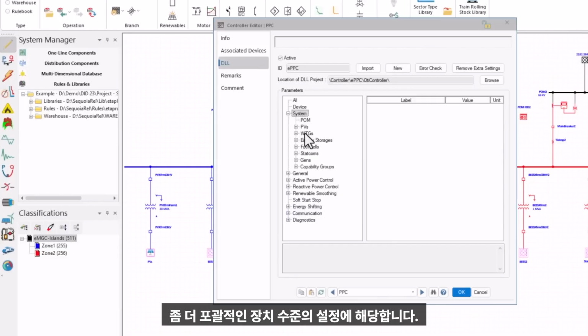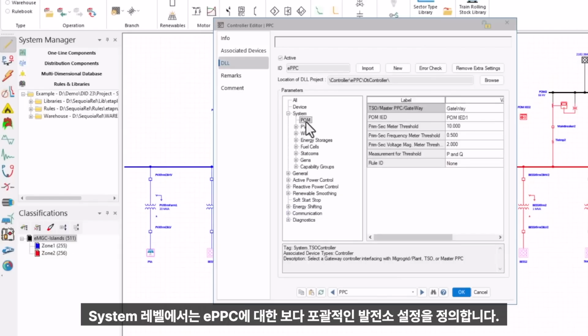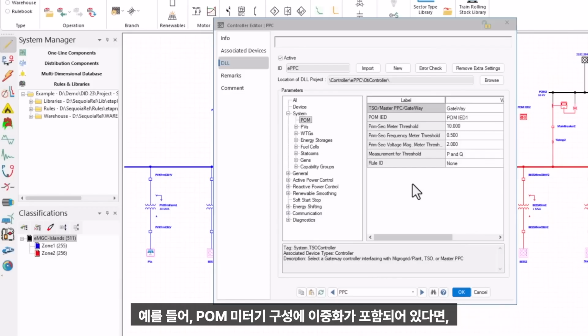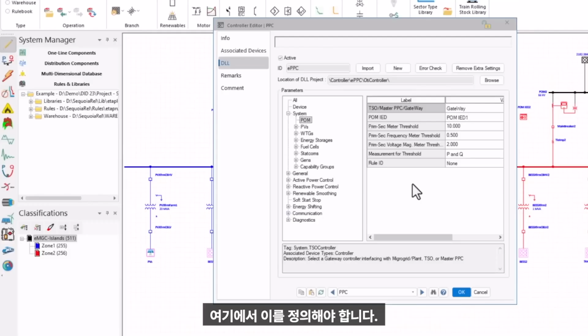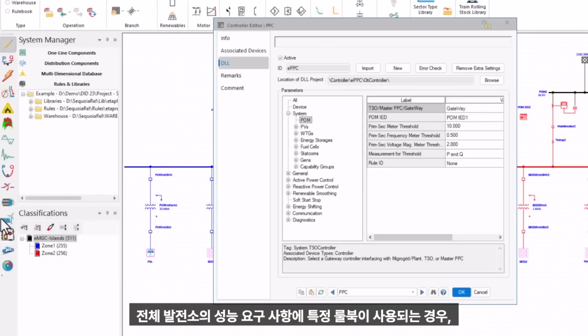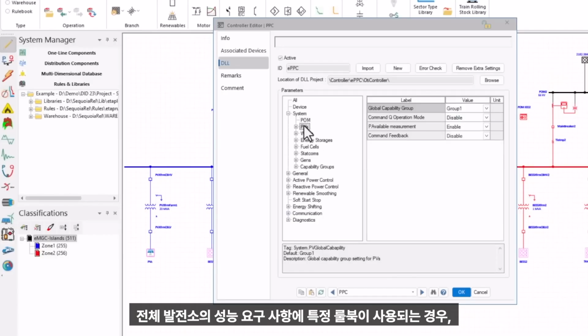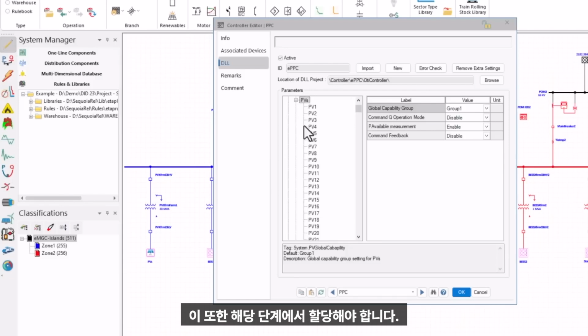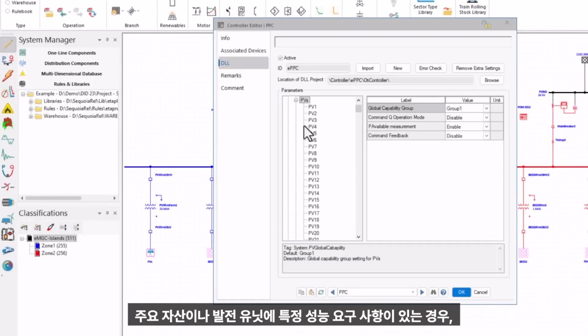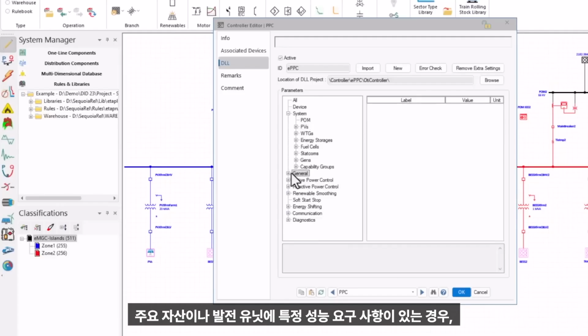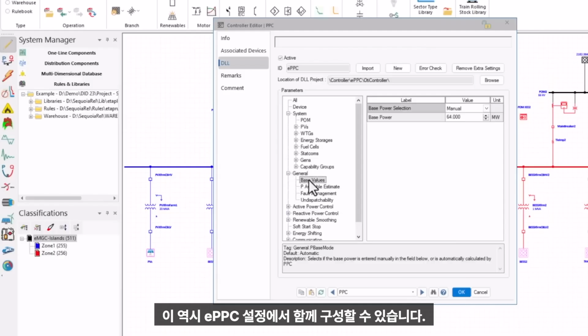At the system level, we define broader plant-level settings for the ePPC. For example, if the POM meter arrangement includes redundancy, that should be defined here. If the project uses a specific rulebook for the capability requirements of the overall plant, that also needs to be assigned here. And if the primary assets or generating units have specific capability requirements, those can be configured in the ePPC settings as well.